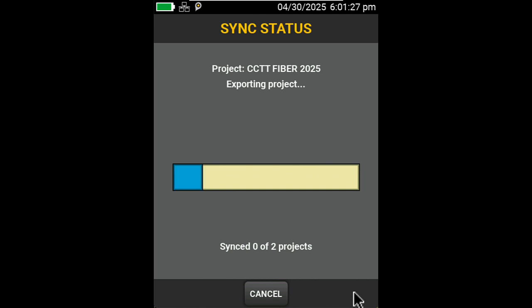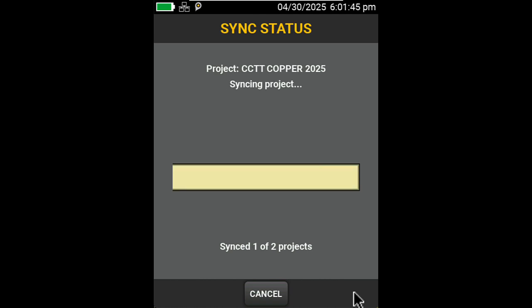It's important to note that in order to be logged into LinkWare Live, we need to be connected to the Internet. On a Versiv 2, this can be accomplished by using the built-in Wi-Fi. On a Versiv 1, we can plug it directly in using the Ethernet port or use a USB Wi-Fi adapter.